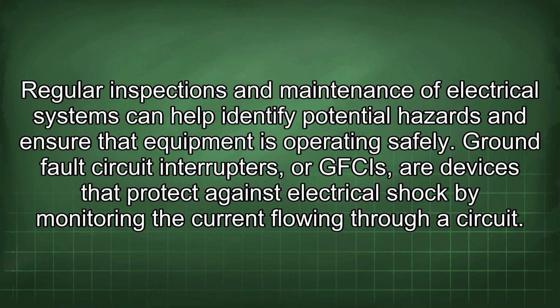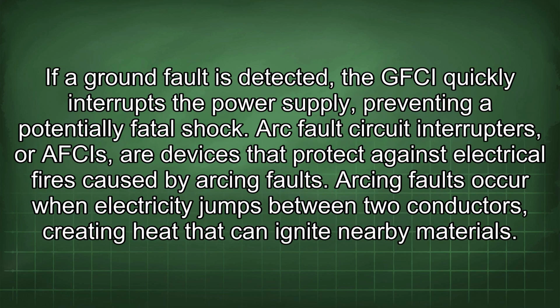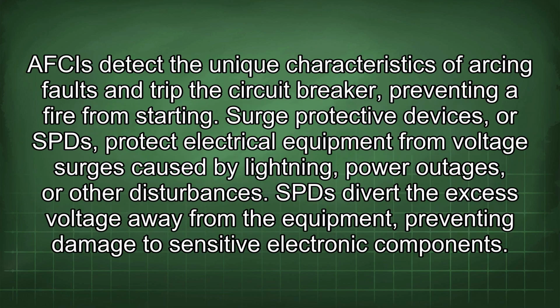Ground fault circuit interrupters, or GFCIs, are devices that protect against electrical shock by monitoring the current flowing through a circuit. If a ground fault is detected, the GFCI quickly interrupts the power supply, preventing a potentially fatal shock. Arc fault circuit interrupters, or AFCIs, are devices that protect against electrical fires caused by arcing faults. Arcing faults occur when electricity jumps between two conductors, creating heat that can ignite nearby materials. AFCIs detect the unique characteristics of arcing faults and trip the circuit breaker, preventing a fire from starting.